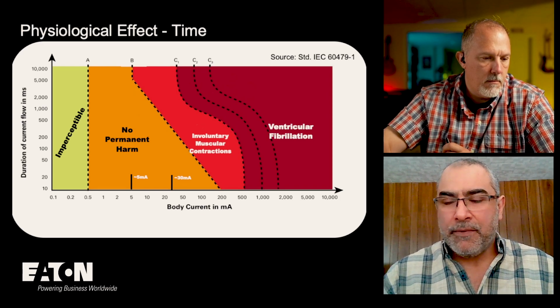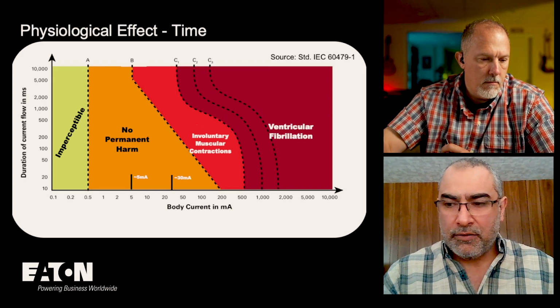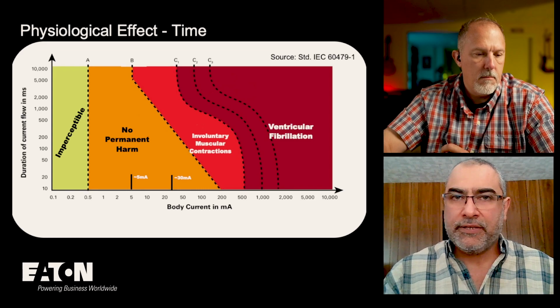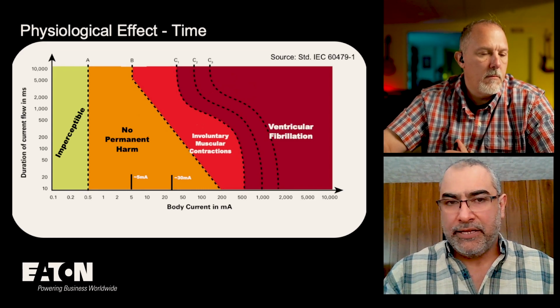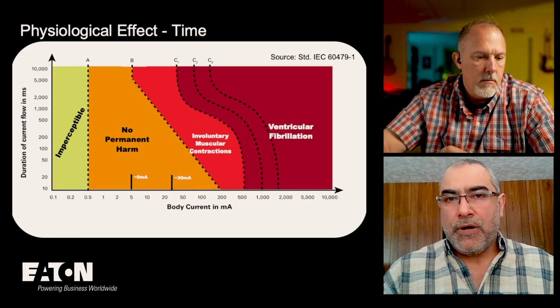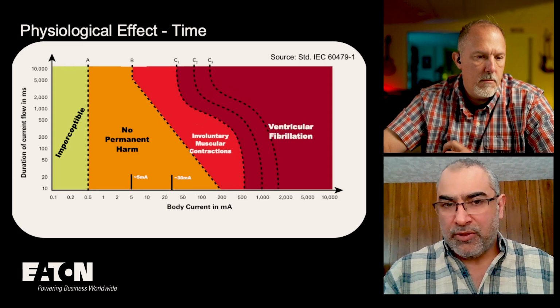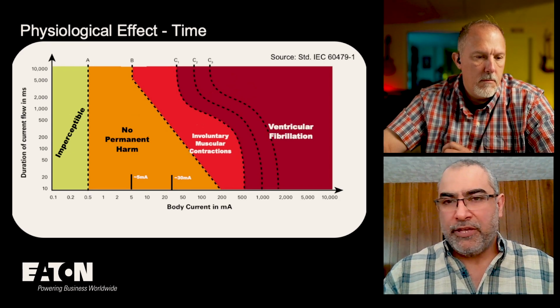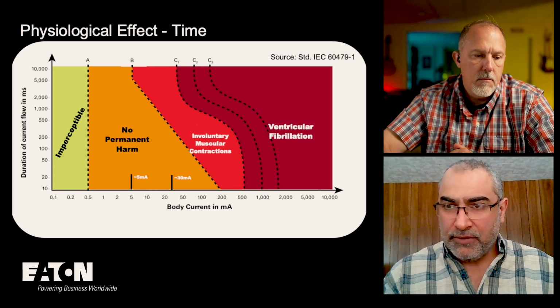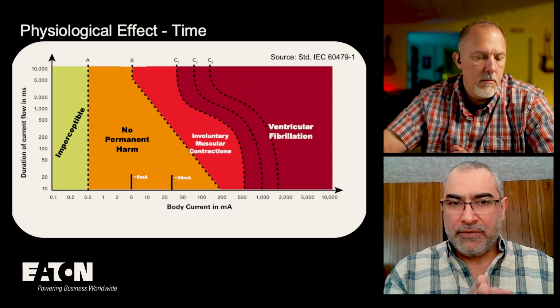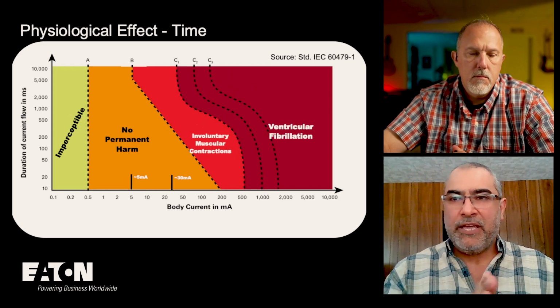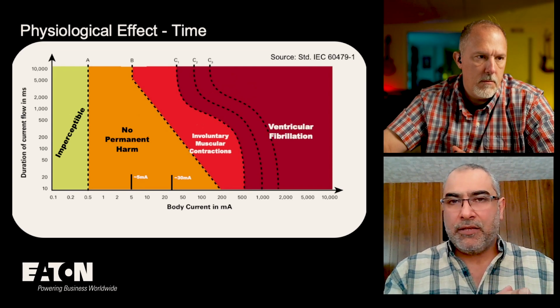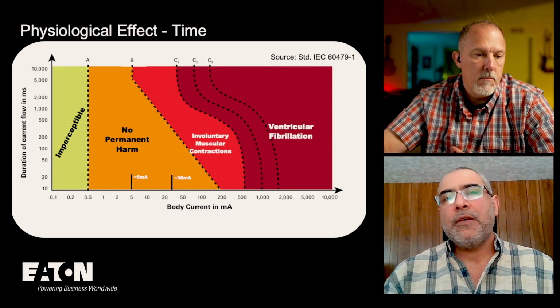At that point in time, it doesn't matter how much time the current goes through the person, you're still not going to get into any harm. So GFCIs are required in North America to trip to provide what they call let-go protection, because at this point most people will still be able to let go without needing the power to be interrupted.